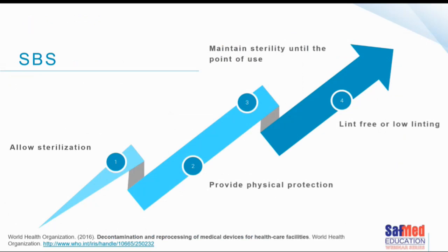Sterile barrier systems need to do several things. Number one, it needs to allow for sterilization — meaning we need to be able to get the air out of a package and get the sterilant to penetrate and do its job. It needs to provide some form of physical protection, maintain sterility until the point of use, and the packaging needs to be lint free or at the very least low linting.